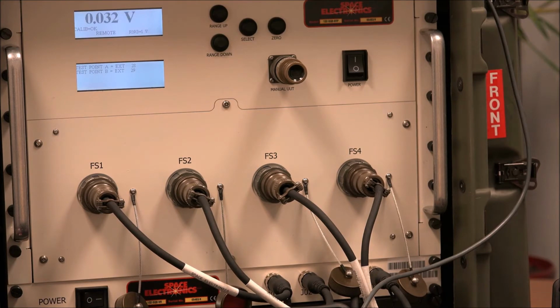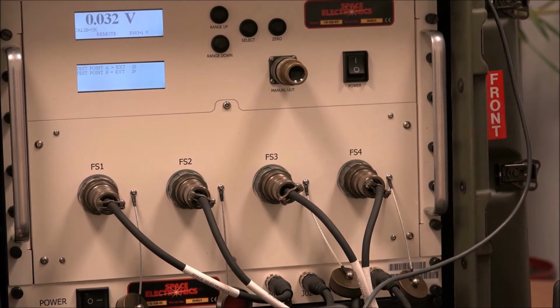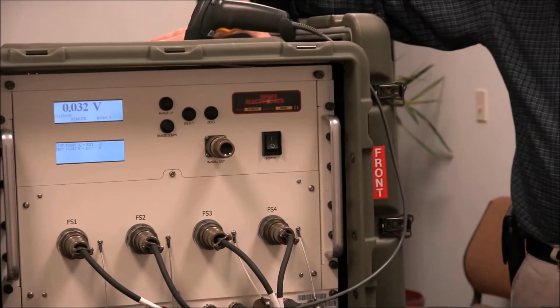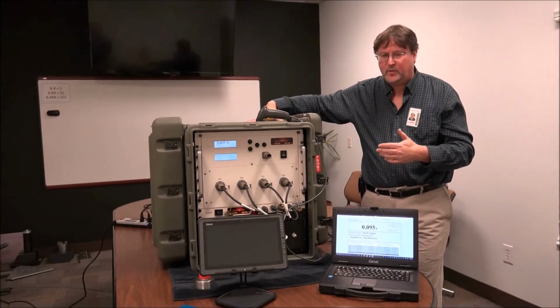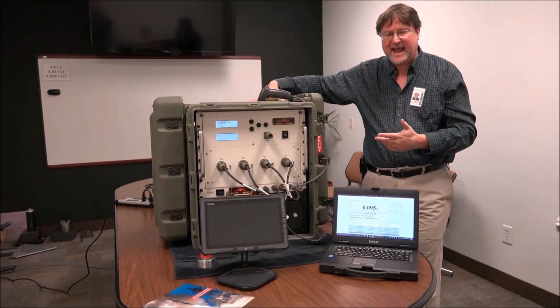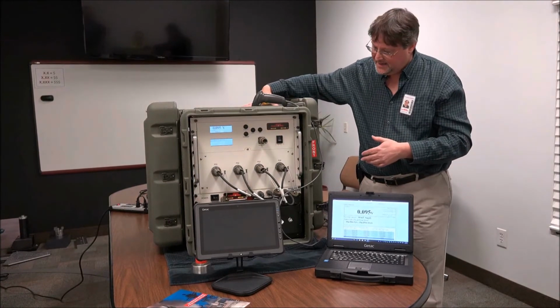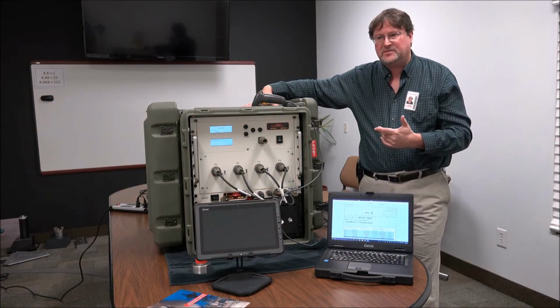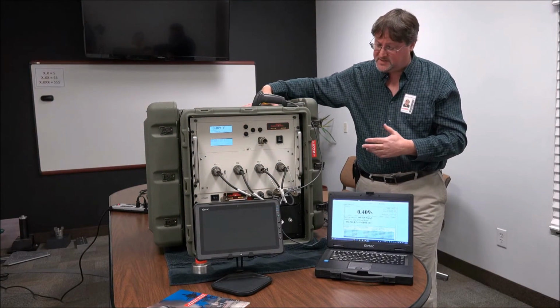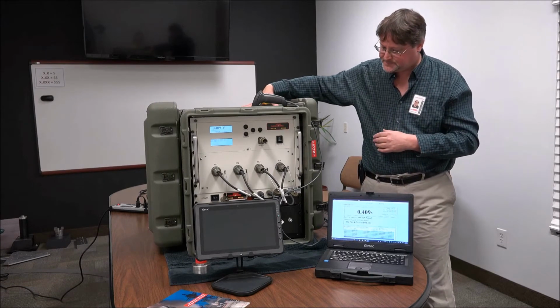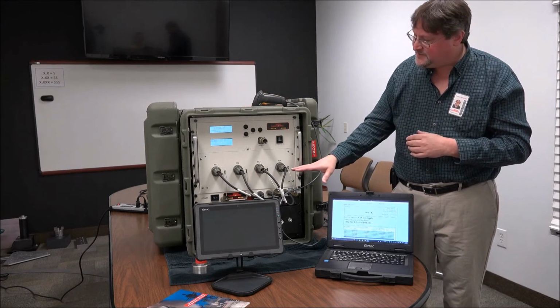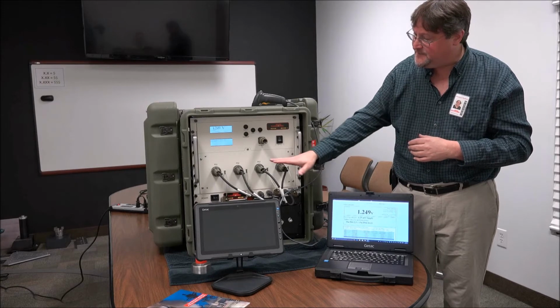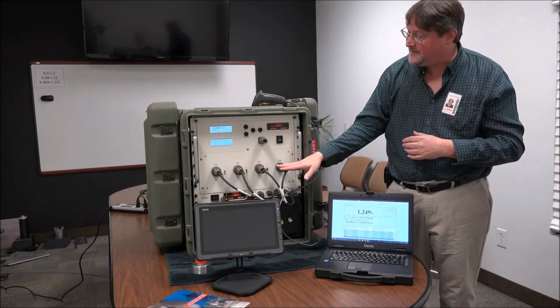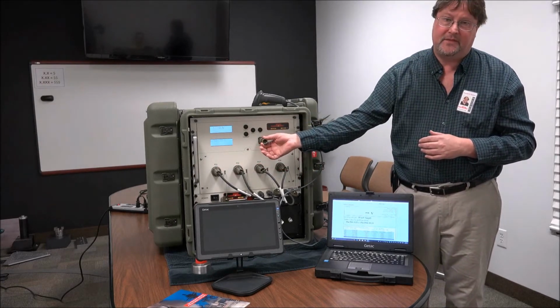We also have a test current. Test current goes down with the range of measurement. So in the case of 20 ohm, the test current is about 2.5 milliamps. In the case of 20 meg, it's about 2 microamps. So the test current varies. The fail-safe current and the test current is the same for the automated test point paths as well as the manual path.